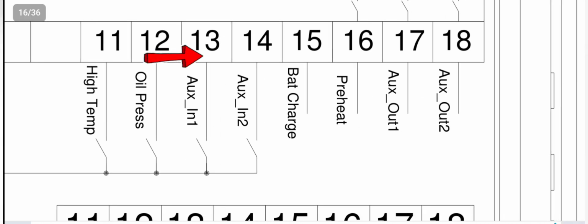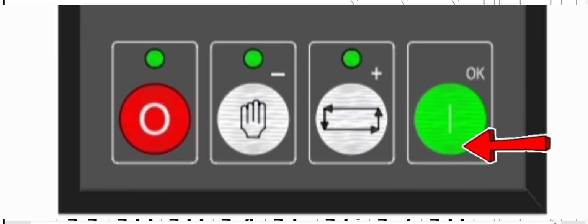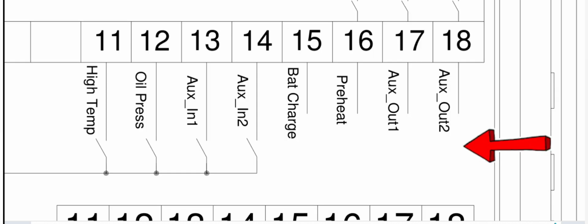And as you can see here, 15 is the battery charge input. This monitors and checks the battery and displays the battery voltage on the screen. Pin number 16 is the output to the preheat. When you first try to start the generator by pressing the green button, this controller keeps on the glow plugs for your pre-programmed 16 seconds, 20 seconds, or 30 seconds. After the delay expires, the generator starts cranking. This is the glow plug relay output, which keeps the glow plug relay on for the period of your delay set point.